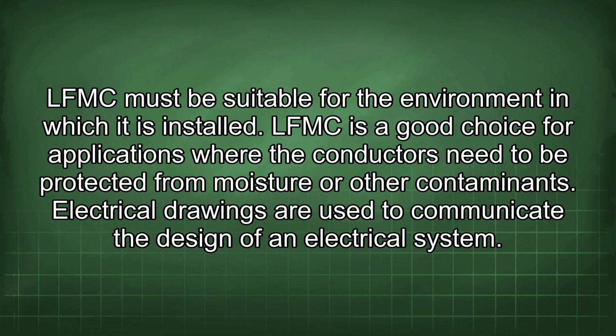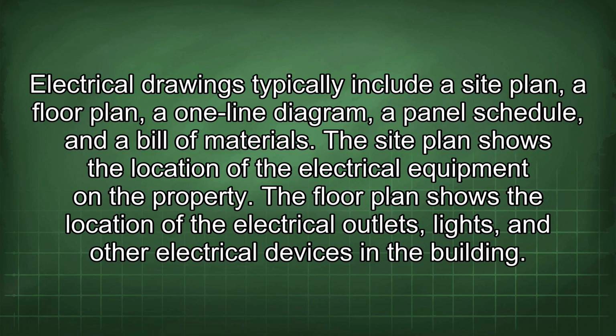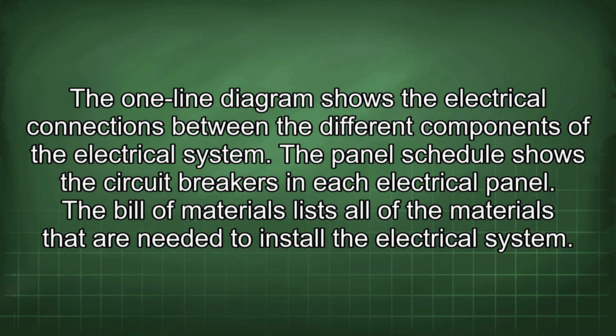Electrical drawings are used to communicate the design of an electrical system. Electrical drawings typically include a site plan, a floor plan, a one-line diagram, a panel schedule, and a bill of materials. The site plan shows the location of the electrical equipment on the property. The floor plan shows the location of the electrical outlets, lights, and other electrical devices in the building. The one-line diagram shows the electrical connections between the different components of the electrical system. The panel schedule shows the circuit breakers in each electrical panel. The bill of materials lists all of the materials that are needed to install the electrical system.